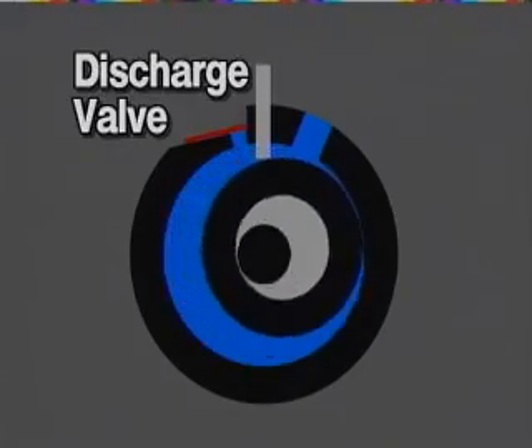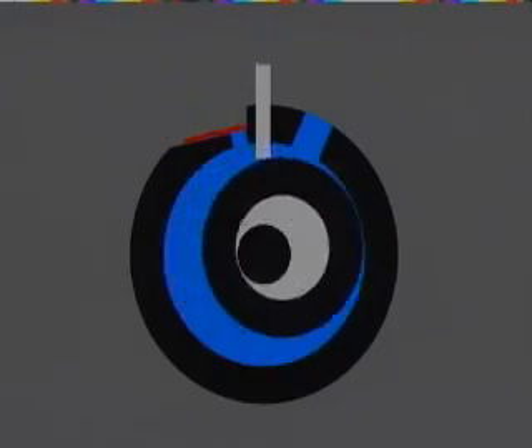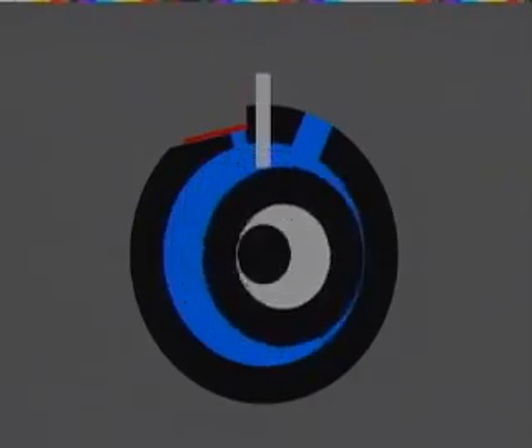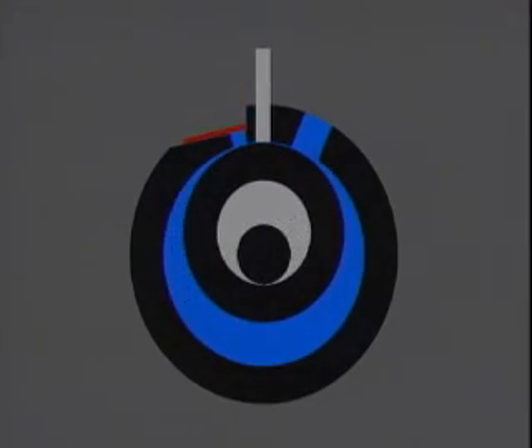The rotary compressor requires only one valve, the discharge valve. Compression and suction occur simultaneously on opposite sides of the rolling piston, so it takes 2 full revolutions of the shaft to draw in and compress a volume of vapor. Let's start with the rolling piston at top dead center.